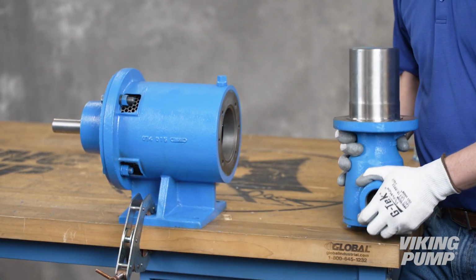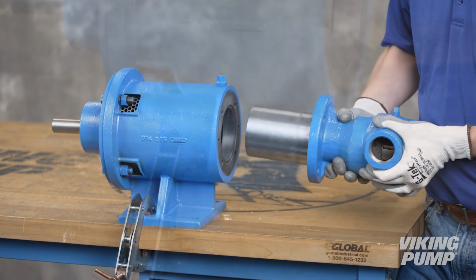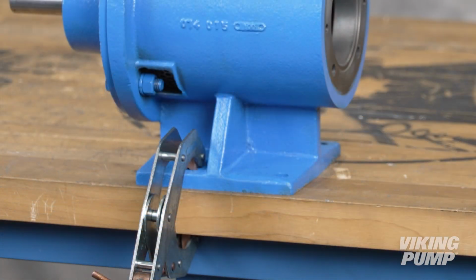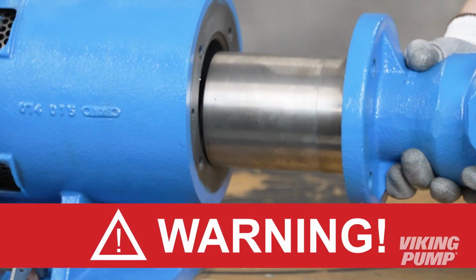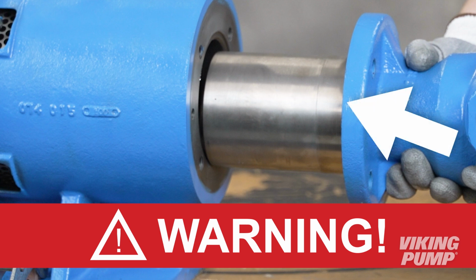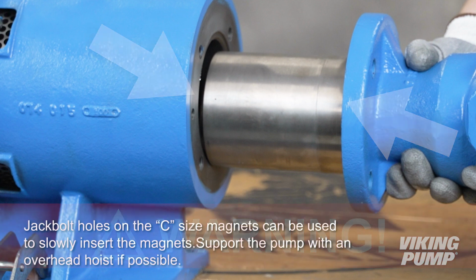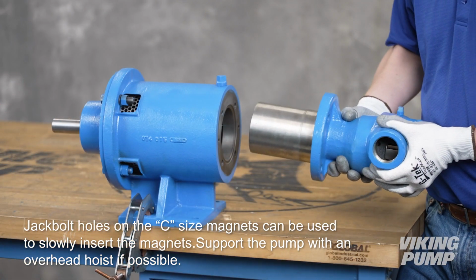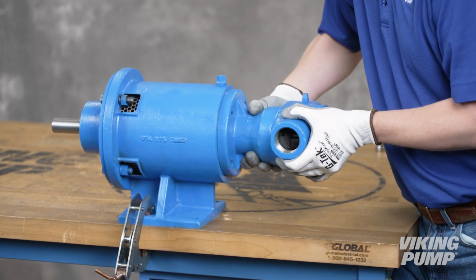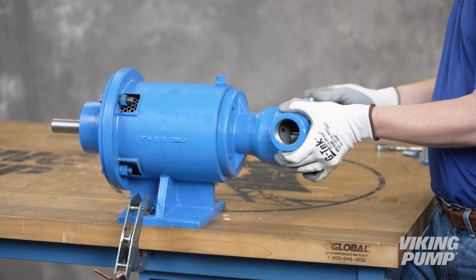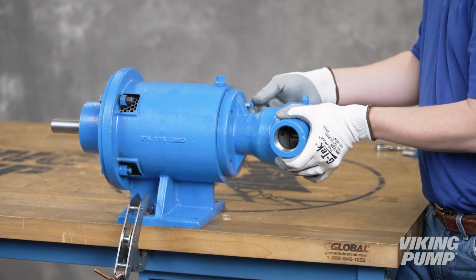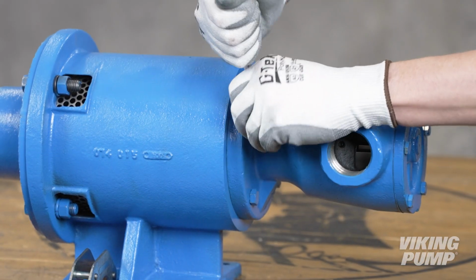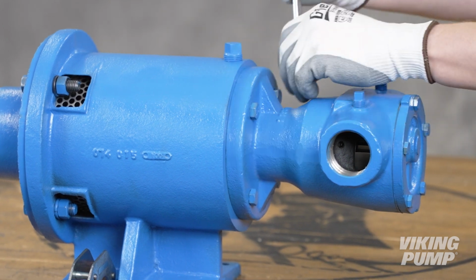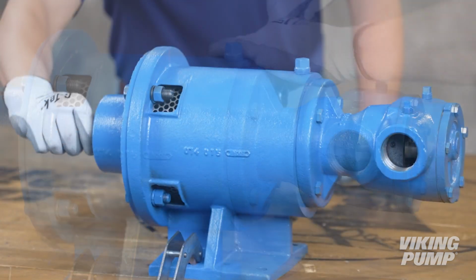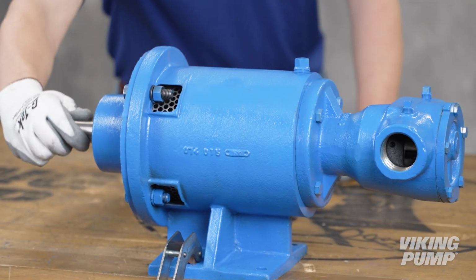Next, place the pump back on the magnetic coupling bracket. Ensure that the coupling bracket is secured. Remember, do not place your fingers onto the front of the pump mounting flange or the face of the bracket. Align the canister into the bore of the bracket and gently slide in. When the magnets start to engage, the unit will finish engagement on its own very quickly. Make sure your fingers are not in front of the pump. Finish the assembly by securing the pump to the bracket by tightening the mounting cap screws. Finally, make sure the pump rotates freely.